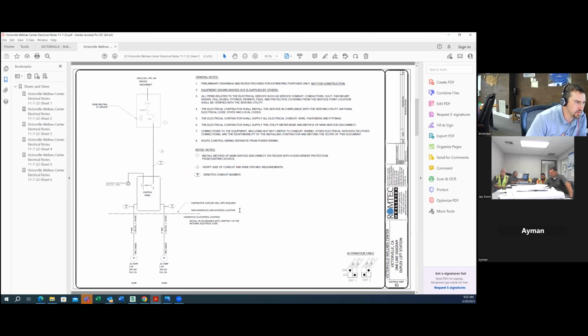So per the NEC, our stance is the NEC requires seal offs into the control panel. So keep that in mind when you're installing these conduits. We like to see seal offs. My engineers like to see seal offs in the conduit coming up into the control panel. So a lot of this will be underground until you pop up and get into the control panel.